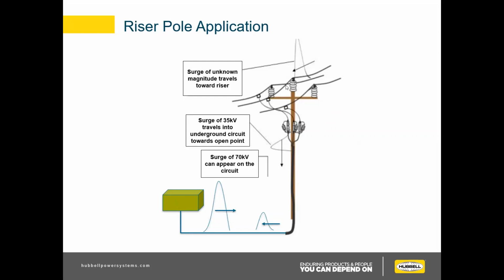So we have a surge current of unknown magnitude traveling down towards the riser. The arrestor shunts it to ground, takes most of the voltage away, and has a discharge voltage of 35 kV. That 35 kV is going to go down the riser and into this box, and it's going to hit that open circuit and come back and double. So you're going to have 70 kV coming back up the line to the arrestor again, super quick. That's why we offer the riser arrestor, because it has a larger MOV block and can handle that second surge of double voltage.